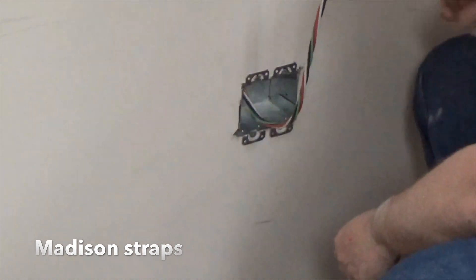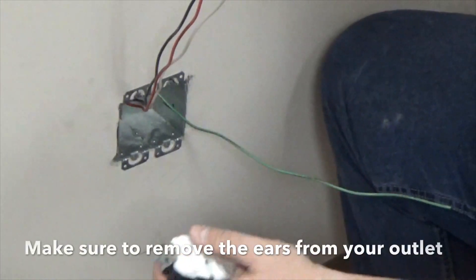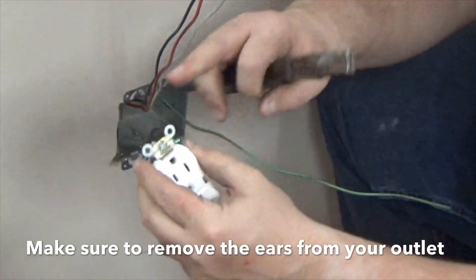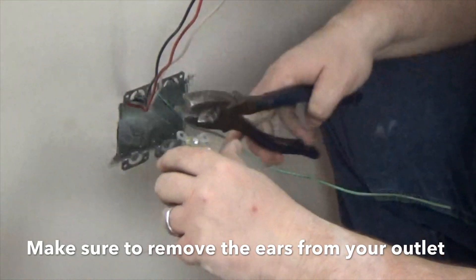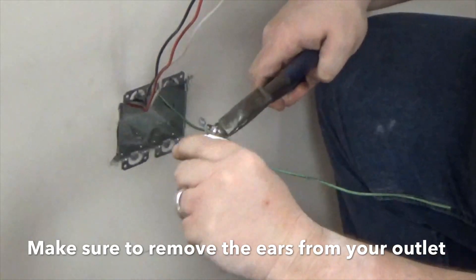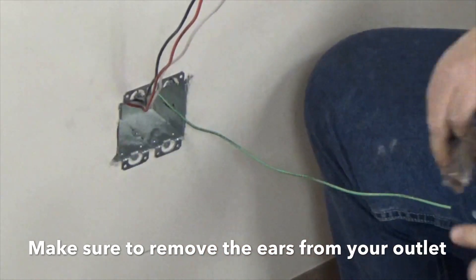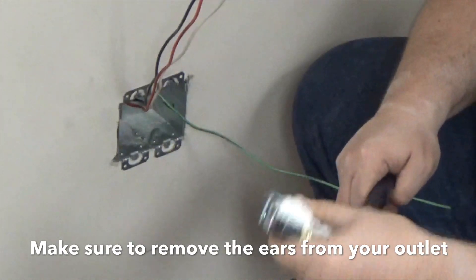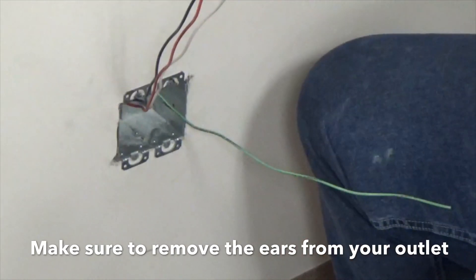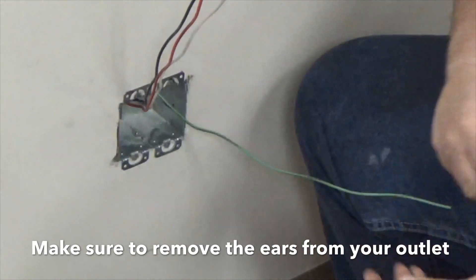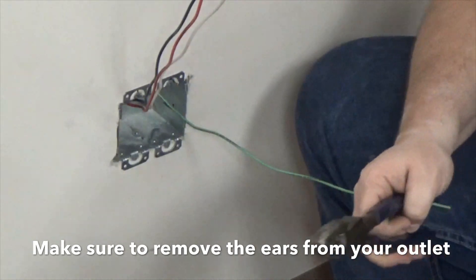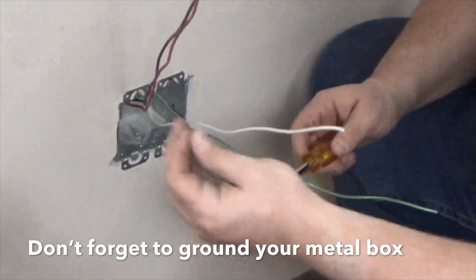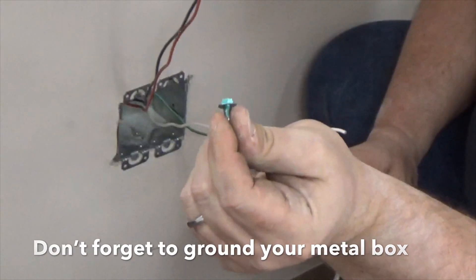Okay, before I connect my outlets, in an old work box, you need to take the ears off of the outlet. You just take them and twist them off. And then your outlet looks like so. Metal old work box, make sure you put your green number 10 grounding screw in.